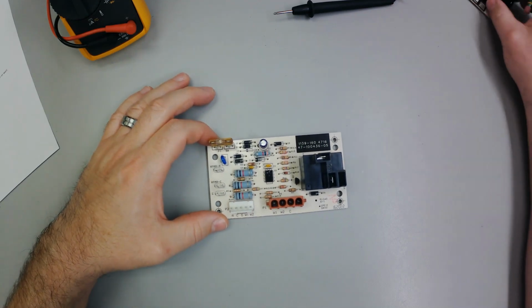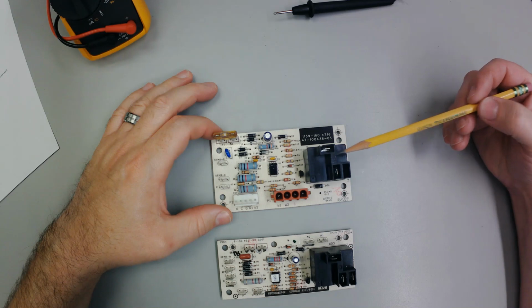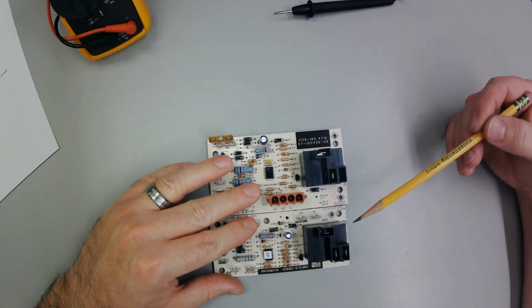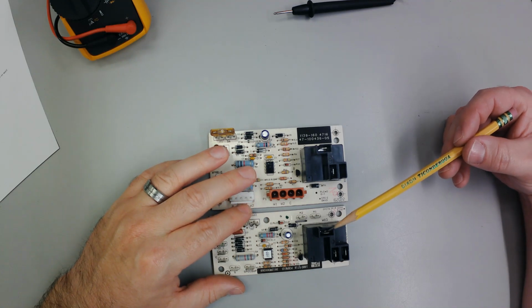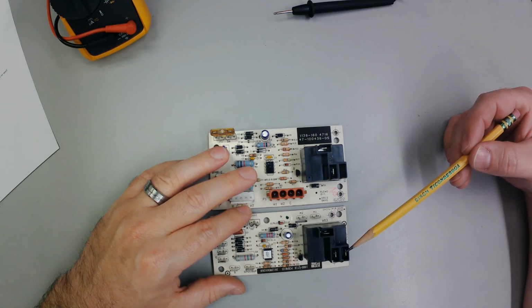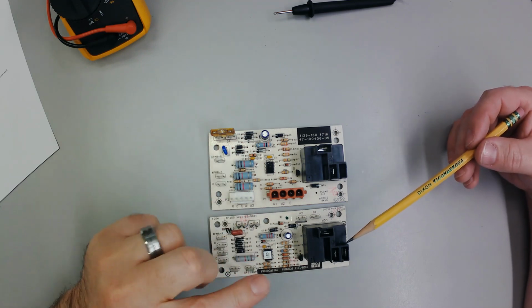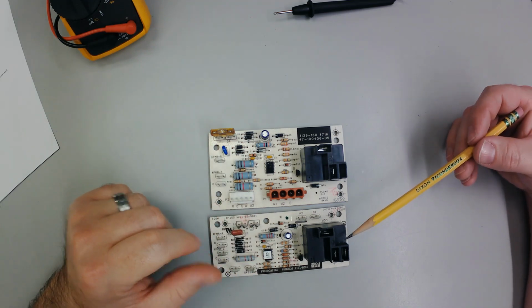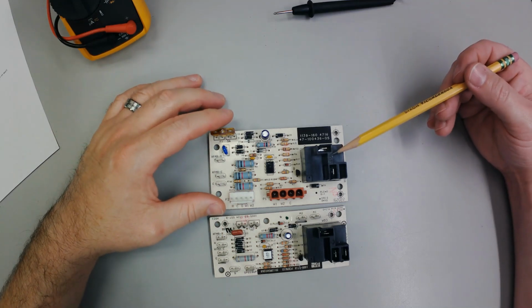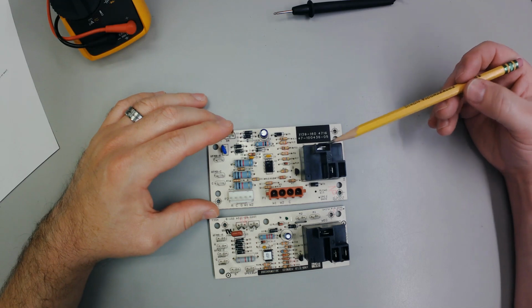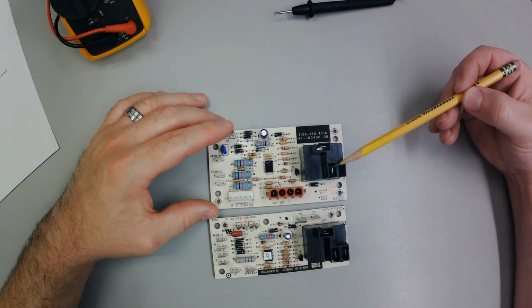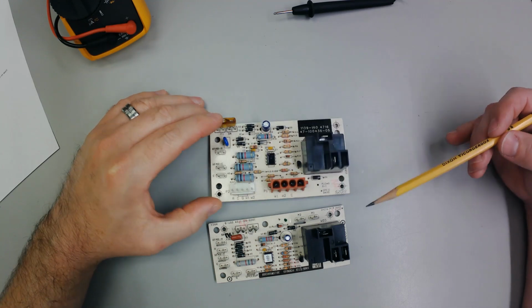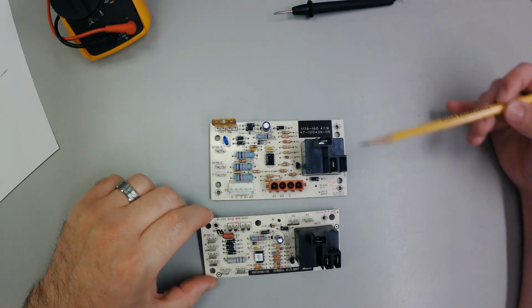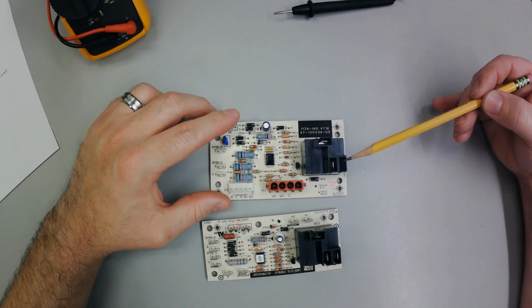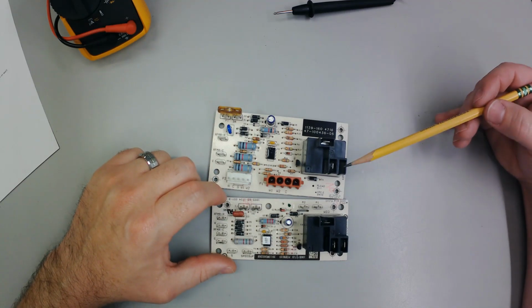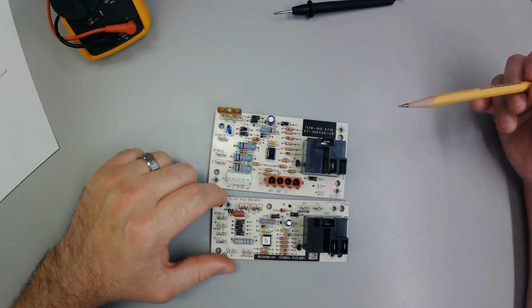This fan relay right here, if you look at it, hopefully you'll notice one thing right away: the Goodman relay had a common, normally open, and a normally closed circuit in that relay. This is typical of the brown relay, the 9340, that you will come across in the field. But this Rheem air handler board only has a common and a normally open. They don't even label it like the Goodman board did. They don't even label it. It's just one switch. They took this part out. You'll see it's the same profile, but they took the normally closed switch out. That's going to be important later. Okay.